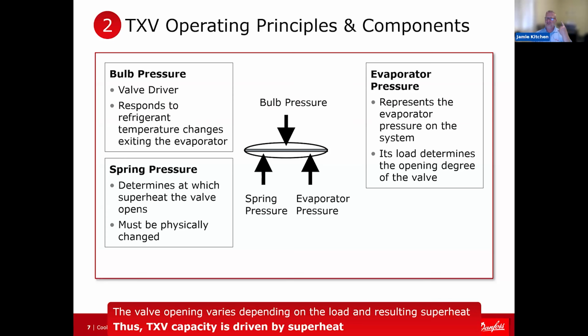So 2 closing forces. The opening force is your bulb pressure. So inside your bulb, you have a secret sauce, right? You have a mixture of gases, refrigerants, things like that. You might have some carbon in there to control the release and how fast it absorbs, opens and closes, whatever. But those are the 3 forces. So when you adjust superheat, what you're doing is you're compressing that spring or you're releasing it. And that means the amount of temperature difference between the bulb and the evaporator is either going to need to increase or decrease to match that.